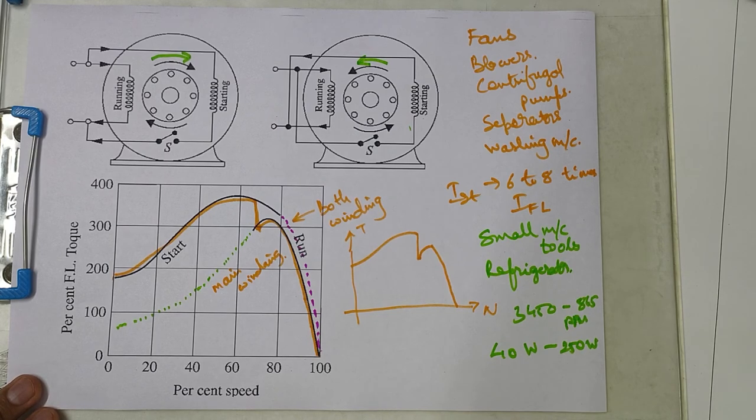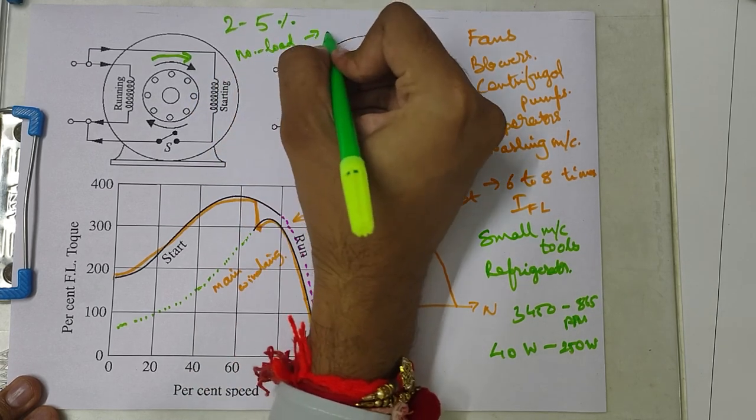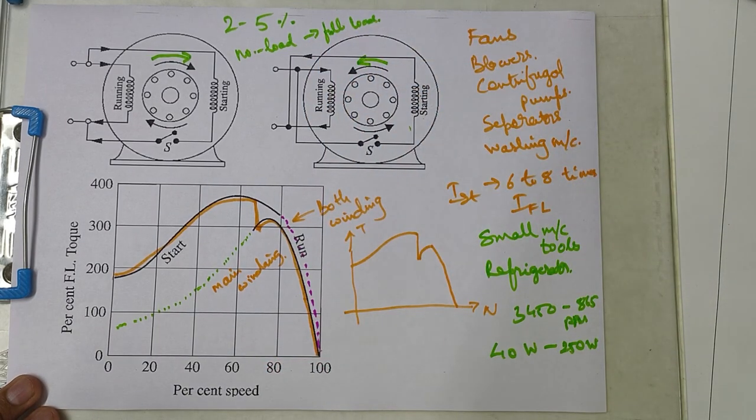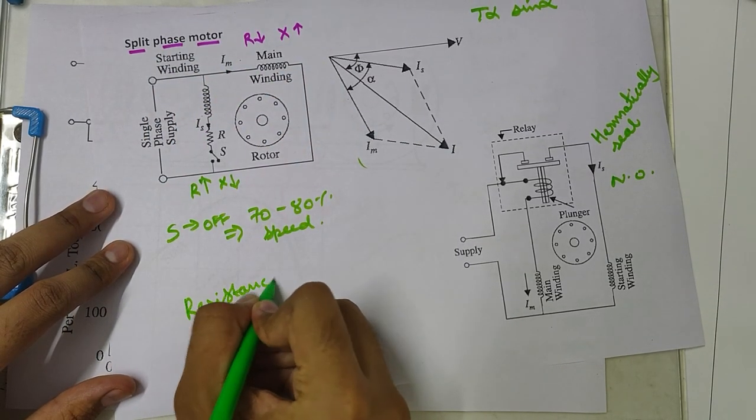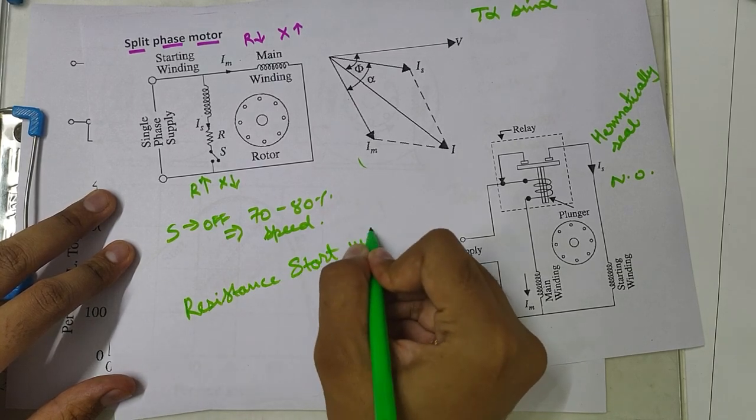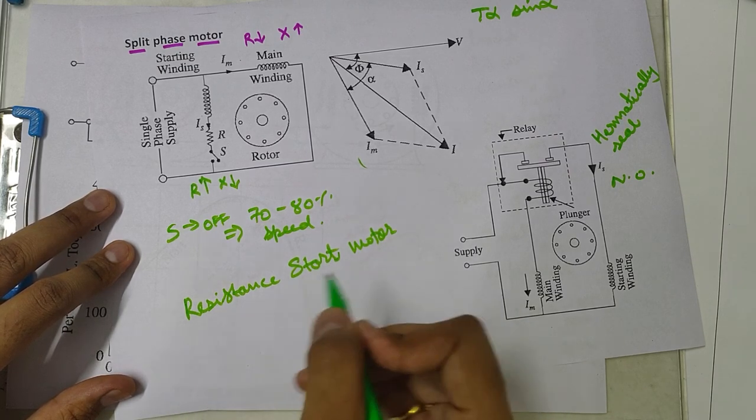These motors are having speed regulation very same as three phase motors. Their speed only varies about 2 to 5 percentage between no load to full load, which is similar like three phase induction motor. And for this reason, such motors are also referred to as split phase motors and also as resistance start motor, just to differentiate with the other term which is known as capacitor start motor.